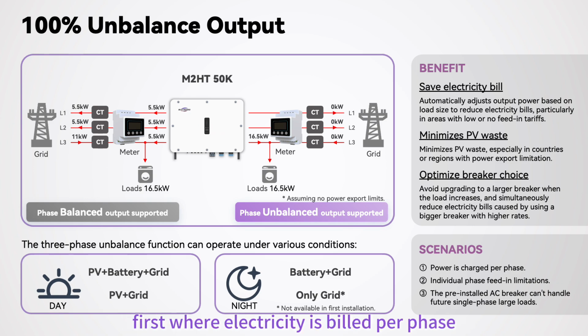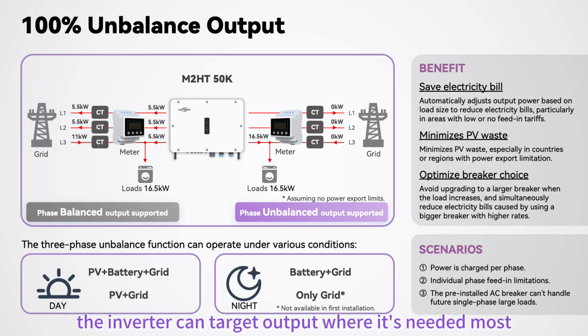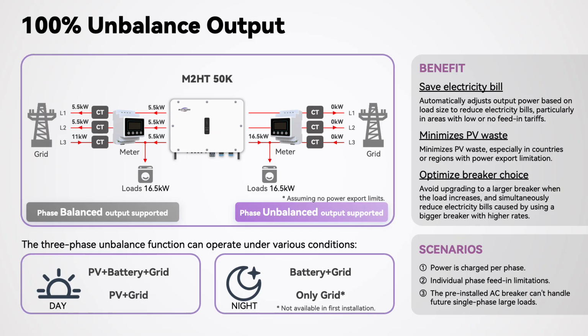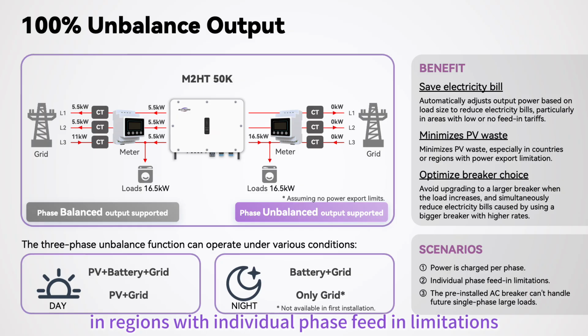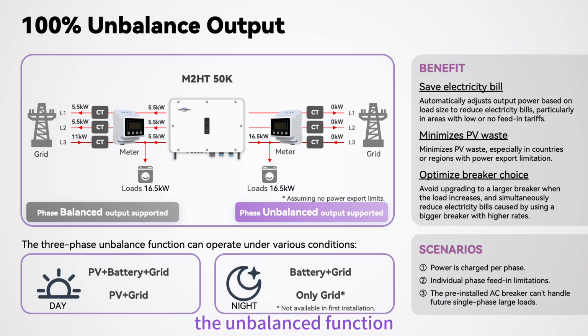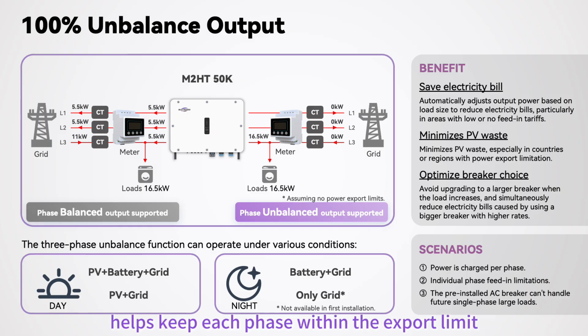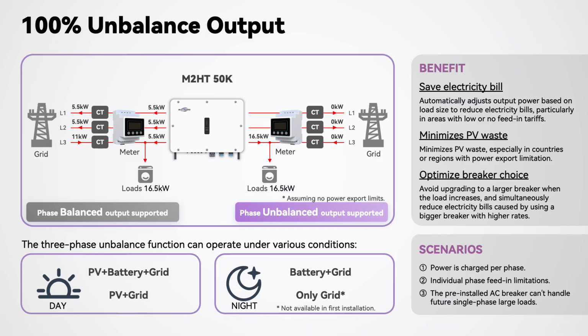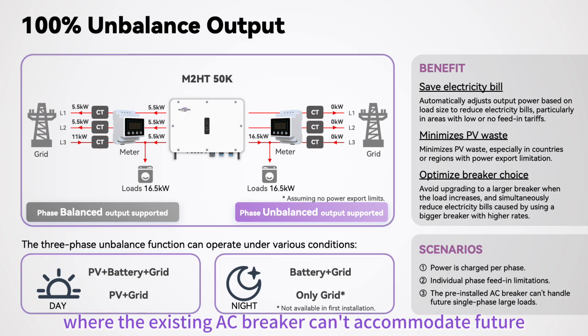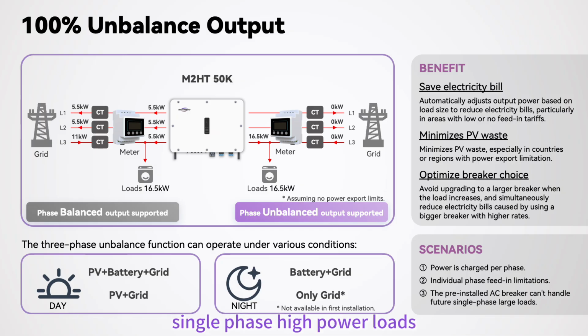First, where electricity is billed per phase, the inverter can target output where it's needed most, directly reducing the bill. Second, in regions with individual phase feed-in limitations, the unbalance function helps keep each phase within the export limit while still maximizing self-consumption. And third, for sites where the existing AC breaker can't accommodate future single-phase high-power loads, the unbalance capability removes the need to upgrade the breaker, saving the end user both cost and disruption.